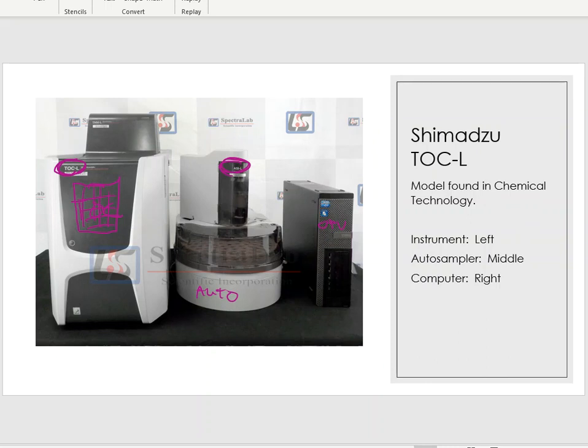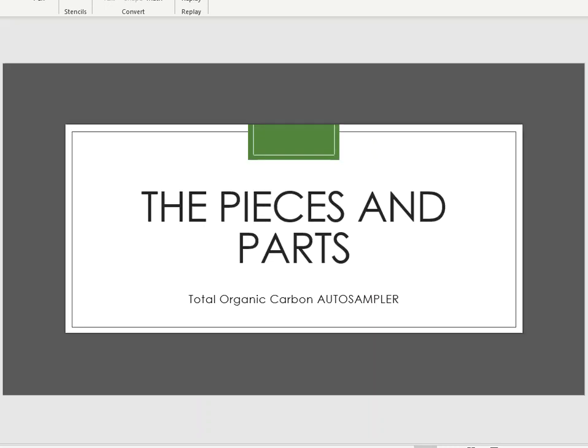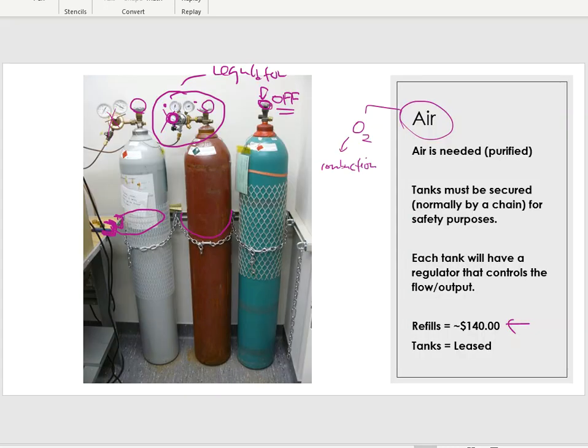That's all for this video. In the next video we'll go into more detail about the auto injector — how it does its job and what components can be replaced or fixed. The key takeaway here is the air tank: it's essential for the TOC to work, so it's important to monitor the fill level and the flow going from the tank into the machine.